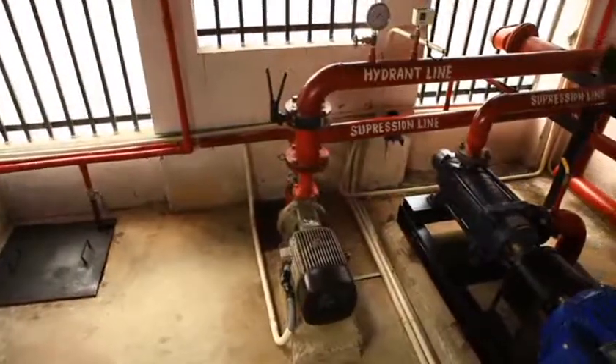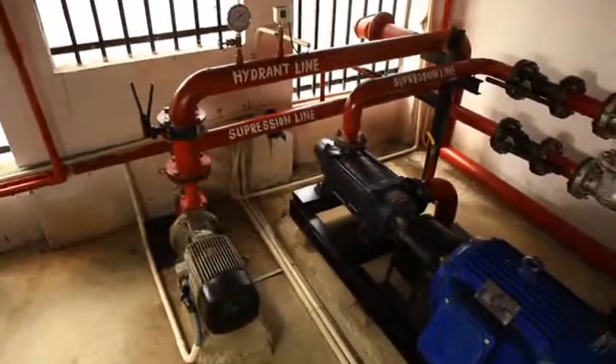The alarm raised by the detectors is registered in the control panel, which actuates the Dry Mist Total Flooding System, either manually or automatically. This releases the extinguishing agents, nitrogen or air, and water. The nitrogen is stored in a cylinder and is let out by a signal from the control panel, and the water, which is stored either in cylinders or supplied through a water distribution system fitted with a filter, is let out at the same time. Both the gas and the water rush through the water mist nozzles, where they're converted into water mist droplets of 25 microns and let out through shock rarefaction waves.